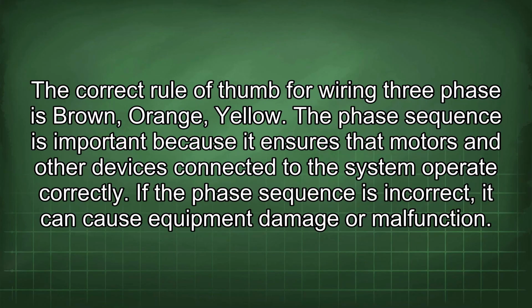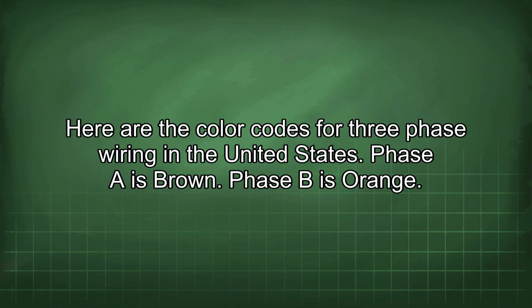The correct rule of thumb for wiring three-phase is brown, orange, yellow. The phase sequence is important because it ensures that motors and other devices connected to the system operate correctly. If the phase sequence is incorrect, it can cause equipment damage or malfunction. Here are the color codes for three-phase wiring in the United States.